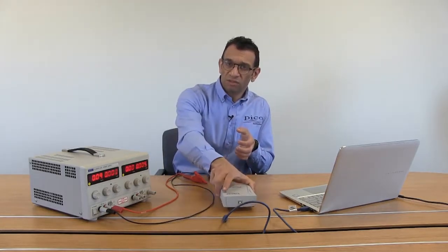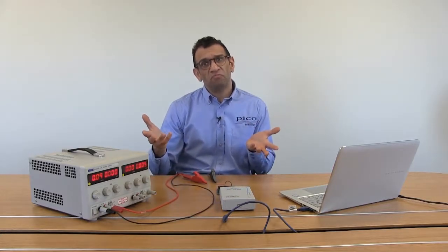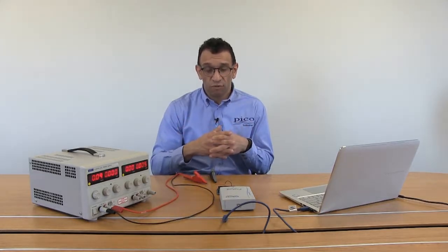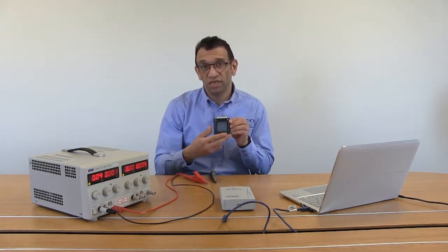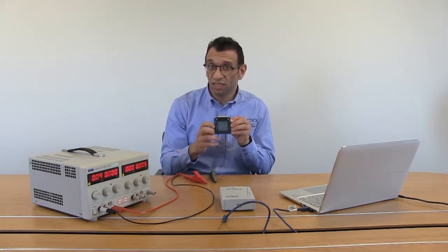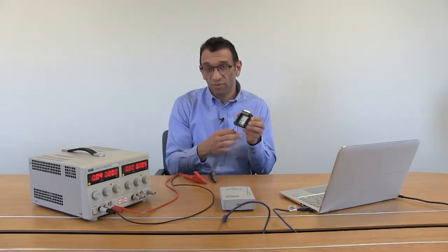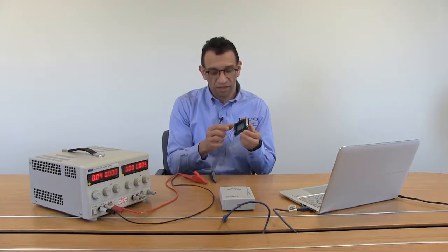So to demonstrate custom scaling, we'll be using the power supply and we'll be feeding an 8 volt signal into the PicoLog 1000, which is higher than its input range, but we'll be using this terminal board over here, and we've got a couple of resistors in there that are dividing the voltage by 4. And we've got a couple of cables here going into channel 10, which is where the potential divider is happening.